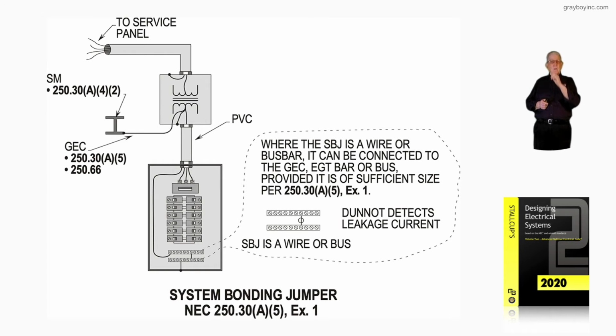Now notice this is one of the cases where the grounded neutral or grounded conductor coming off the secondary side of that transformer would connect to a bar that's isolated instead of directly to the bar that is connected to ground. This exception 1 would allow such a type of installation as you see. And then notice again we have PVC, so that the way that bar is isolated and one bonded into the enclosure there, there's no parallel path there at all, so we can have the XO bonded to the enclosures you see at the transformer and connected into the structural steel, which those sections we have already reviewed and talked about.